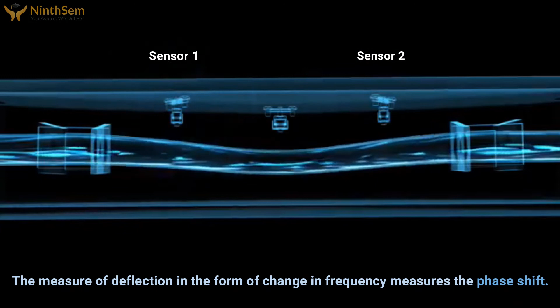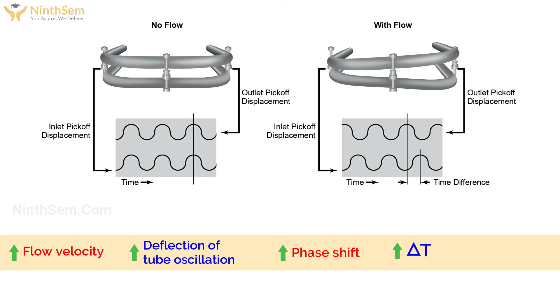This phase shift in the form of a sine wave, you can see in figures 2 and 6. The phase shift of the sine wave in the form of change in time is in microseconds. This phase shift thus measures how much fluid or gas is flowing inside the tube. The higher the flow velocity, hence the total flow inside the tube, the greater the deflection of oscillation, which causes more phase shift in the sine wave, so the change in time is more, hence the flow rate is higher.